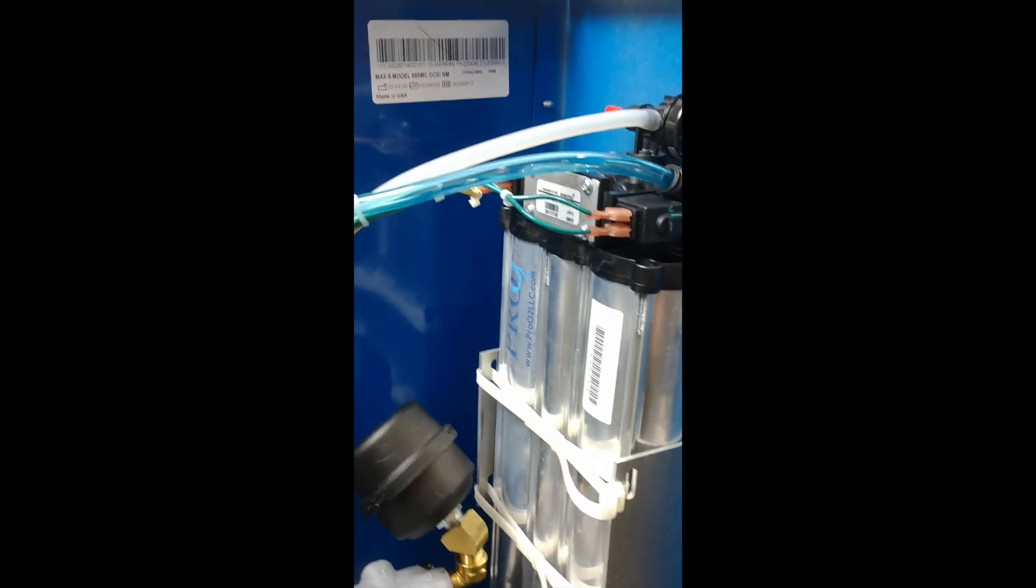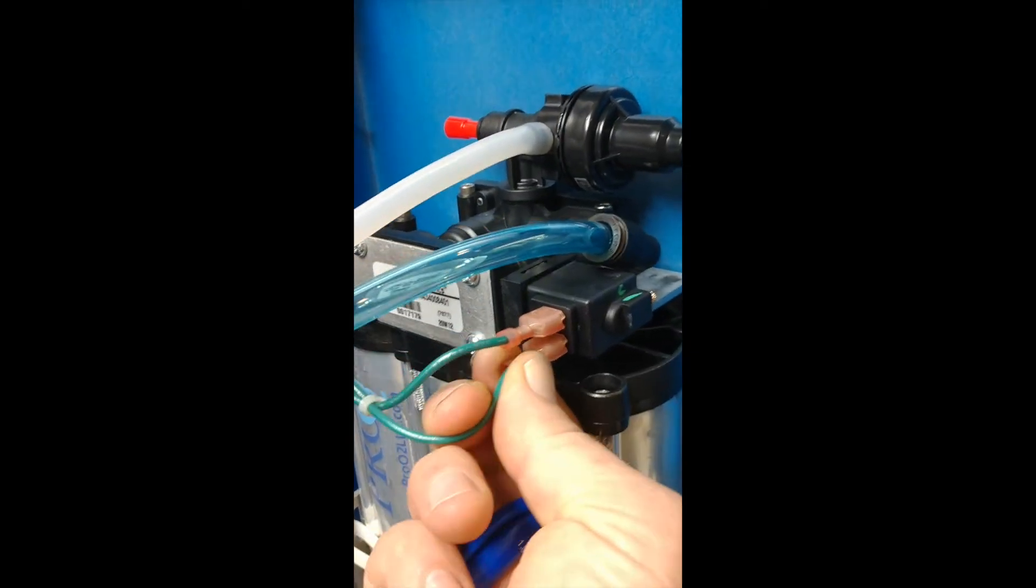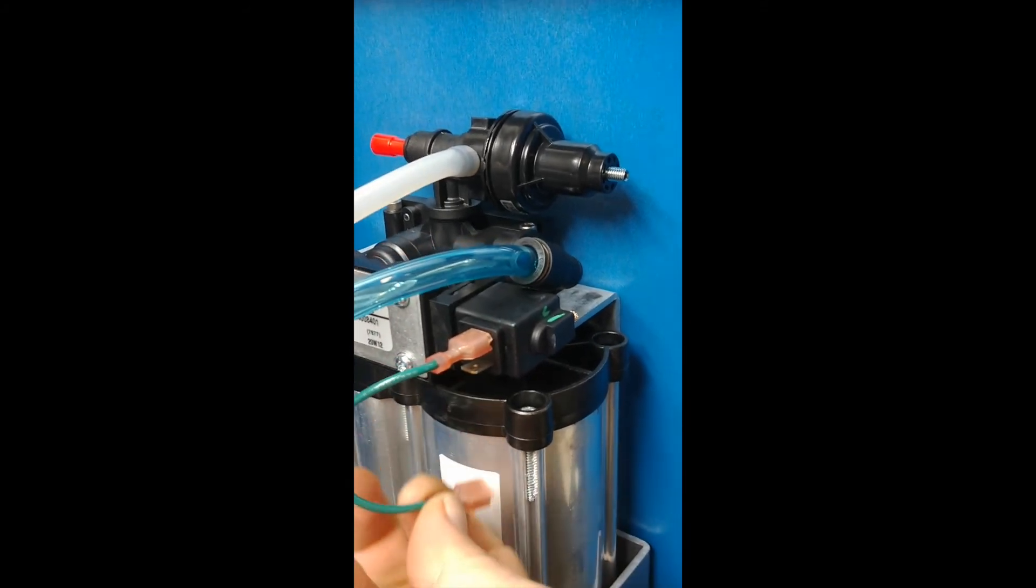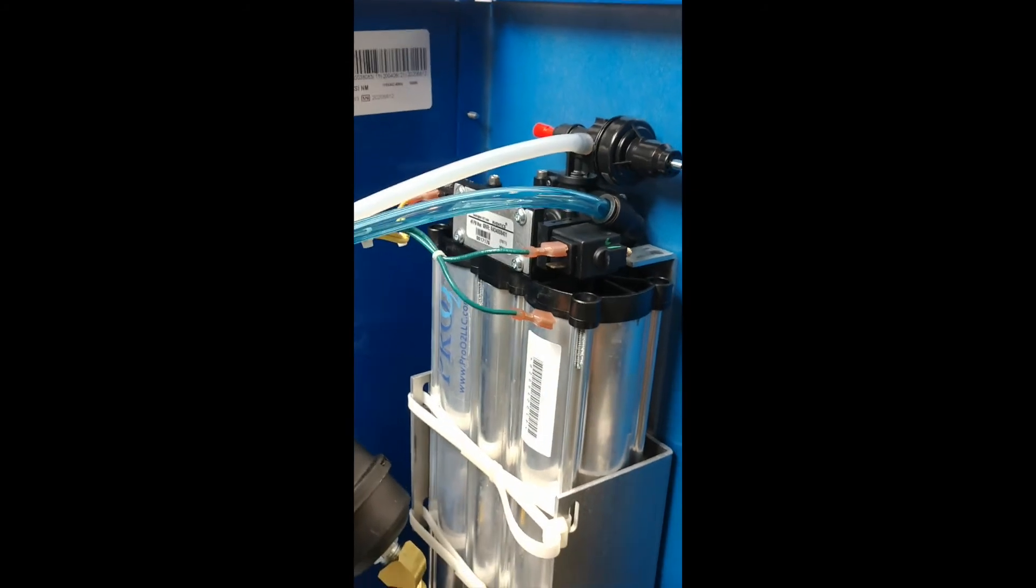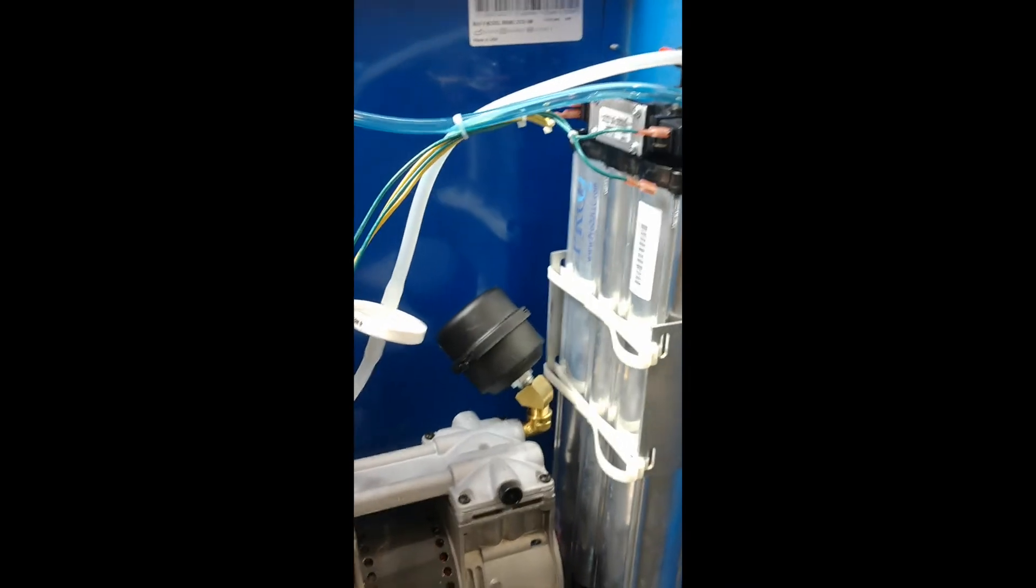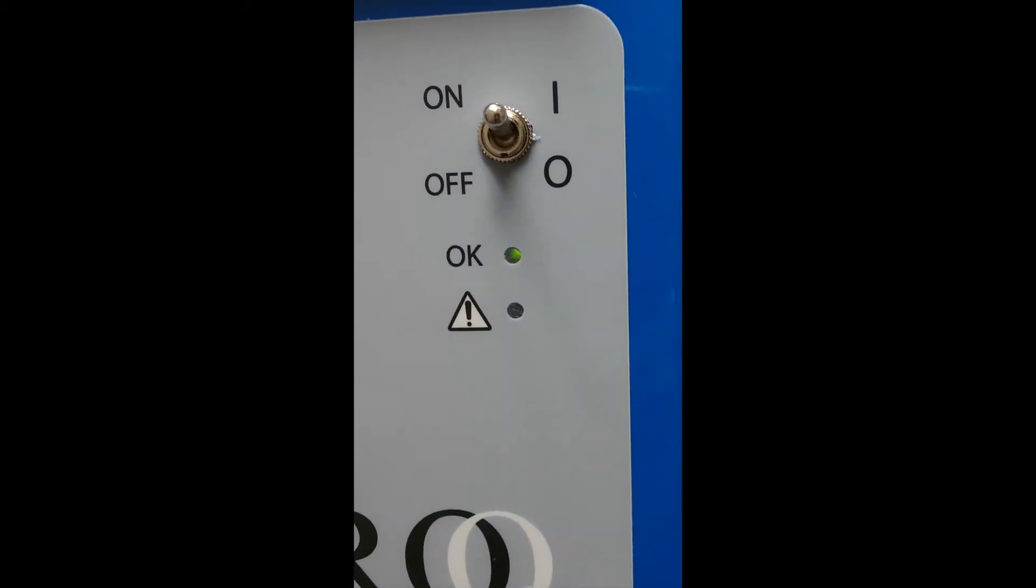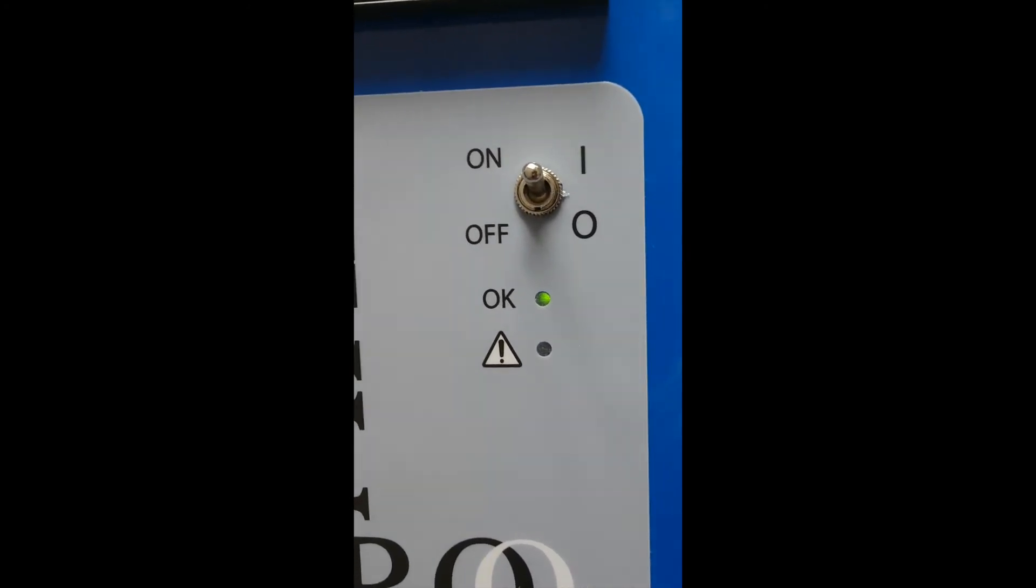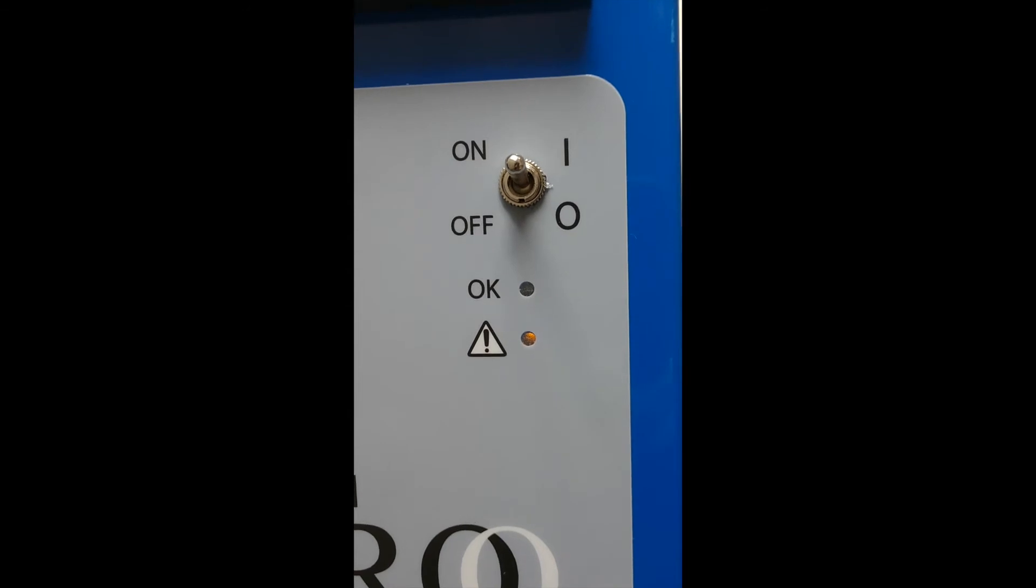Another thing that could happen is your oxygen purity would get low, and I can simulate that by just removing the plug on one of these. Your oxygen concentrator would not be working the way it should be. Eventually your oxygen purity gets low, and it should set off an alarm here pretty quick. It takes a little while for the purity to reduce. One side, there we go.